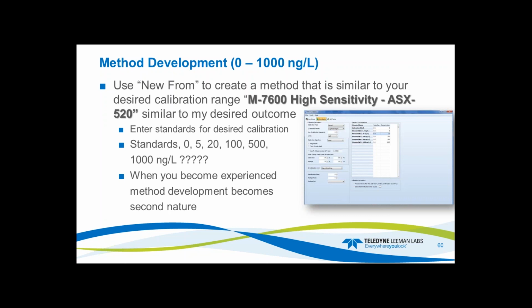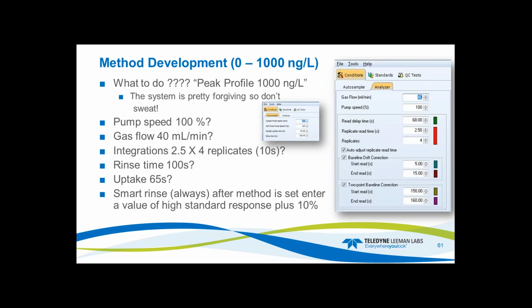But basically, when you become experienced with method development, it becomes second nature, and it's really, really easy to run this system. So we peak profile the high standard, and the system's pretty forgiving, so don't sweat it. The pump speed's 100%, gas flow is 40, and this is the default method. Integration is 2.5 times 4 replicates, which gives me 10 seconds. Rinse time 100 seconds, uptake 65 seconds. Smart rinse, always have it on, but don't set it until after you know your response for your high standard.